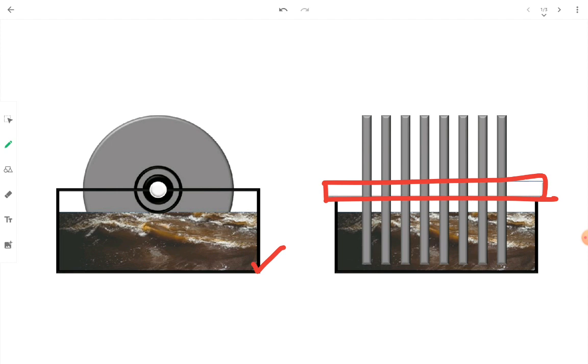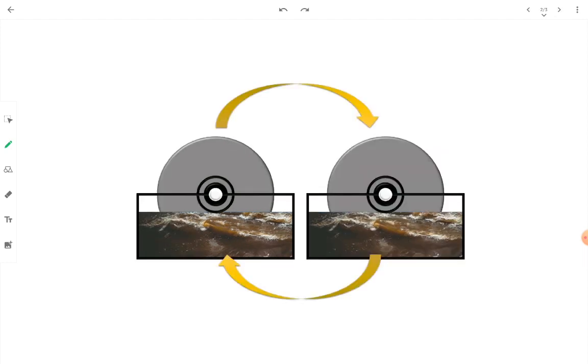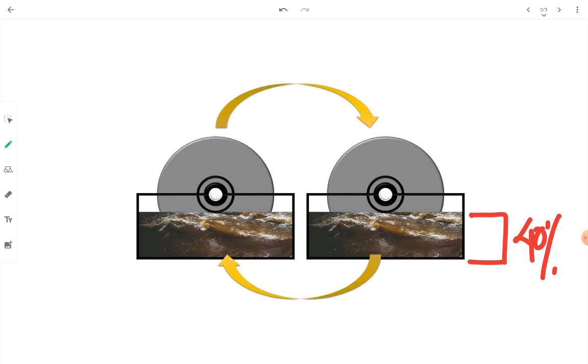Now let's see how RBC works and carries out biological treatment of wastewater. The submergence of the disc is kept at about 40% and the shaft continuously rotates in the unit. Since the shaft is rotating, the disc continuously rotates in a cycle of submergence in wastewater and exposure to atmosphere.